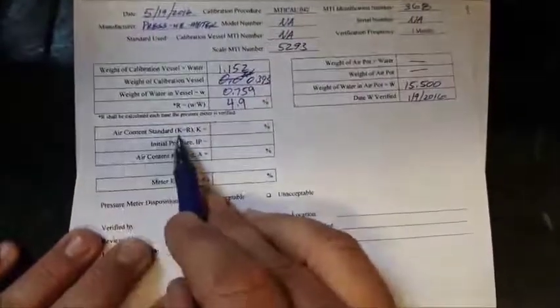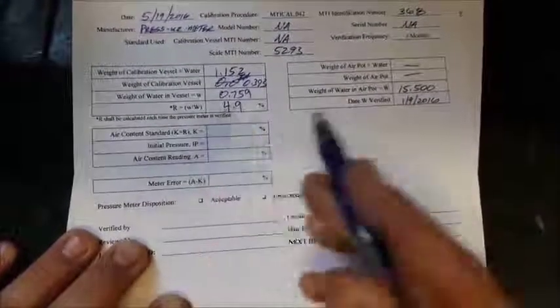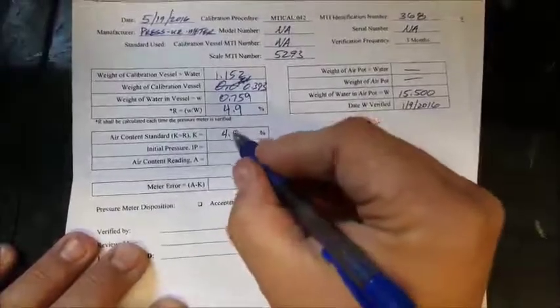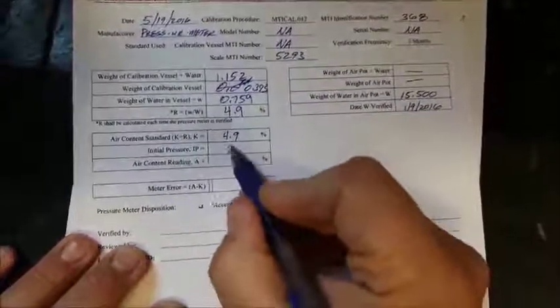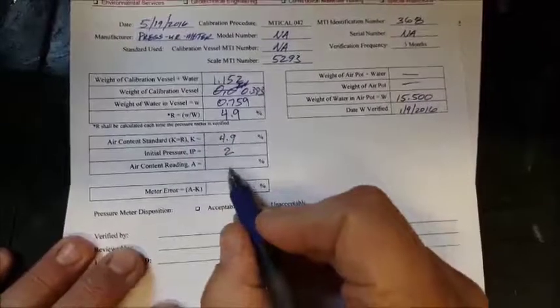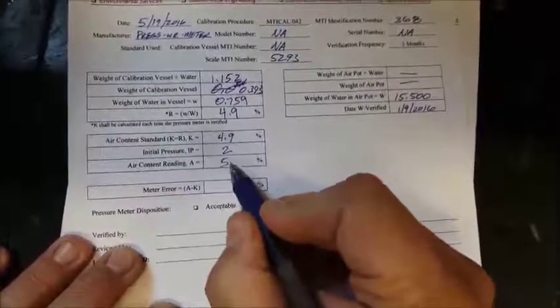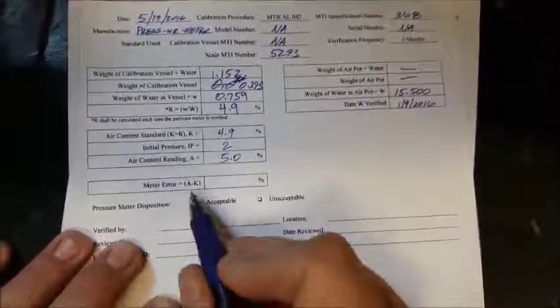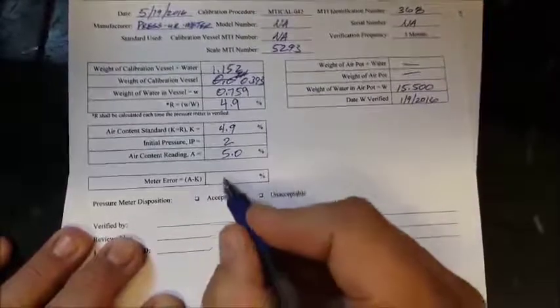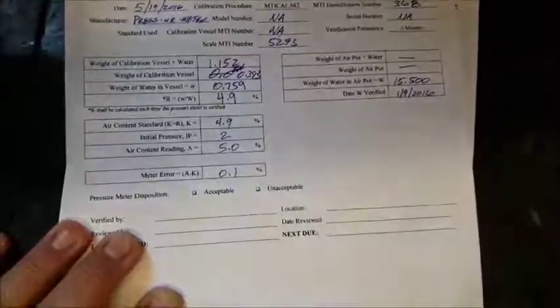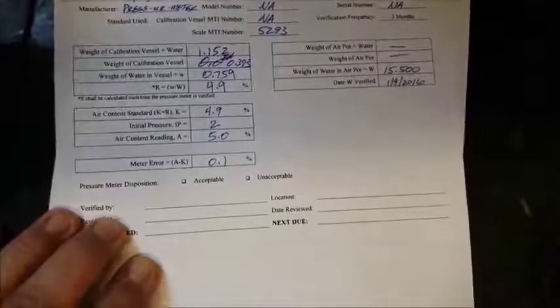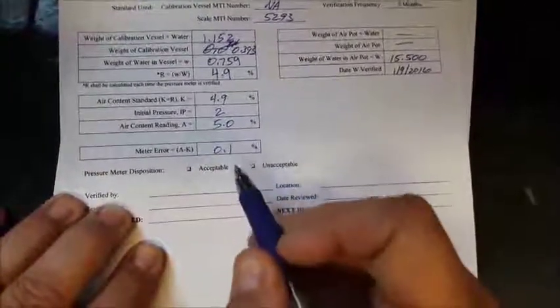So to finish up our worksheet here, our air content standard, K equals R, and R up here was 4.9. We used an initial pressure of 2, and our air content reading from the gauge was 5.0, giving us a meter error, A minus K, of 0.1%. You're allowed 0.1% error. Anything over that is not acceptable, and you would have to recalibrate. So this one ends up acceptable.